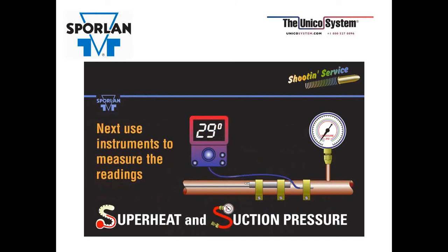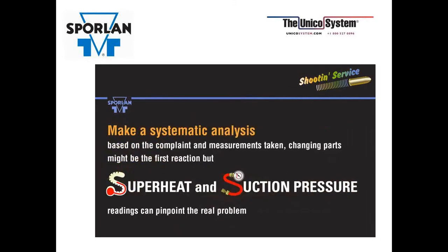And then you want to use your instruments and take good measurements of your superheat and suction pressure. You don't want to guess. In this case, "beer can cold" won't cut it. Take good measurements using reliable equipment. The relationship of the superheat and suction pressure is a nice, reliable guide for system analysis. So then make a good systematic analysis based on the complaint that the customer is telling you and the measurements you're taking. And the first reaction might be to change parts.